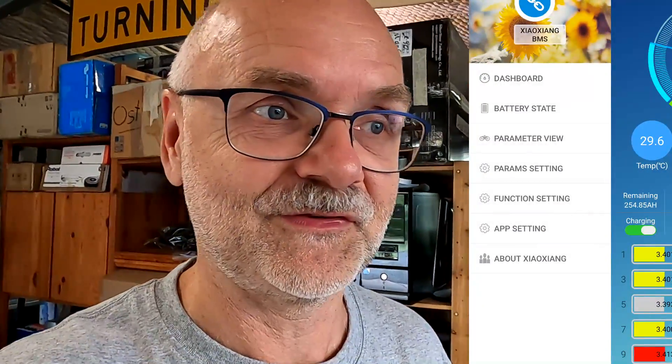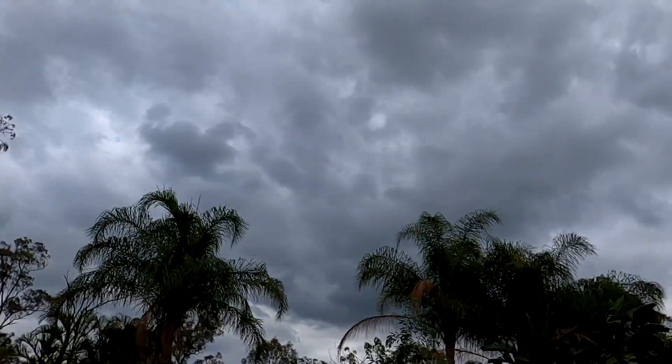That's what I found last night. Today I want to do more testing with you on camera, live. I've turned off the balancing function of the Xiaoxiang BMS so there's no interference — I just want to test the Neey active smart balancer. The weather's gone cloudy, which is frustrating since I need solar to recharge. We're at 98.4% charging at 10 amps, so it shouldn't be too much longer until the battery hits 55.2 volts, which is 3.45 per cell.